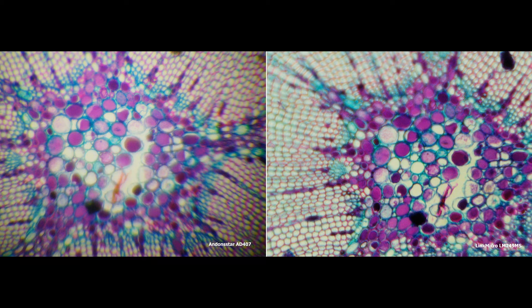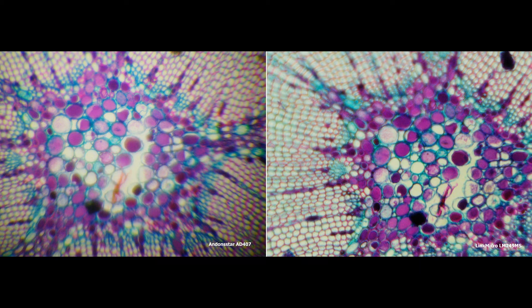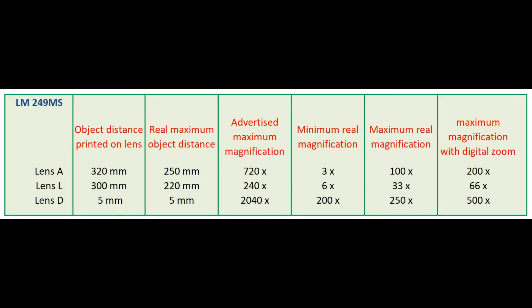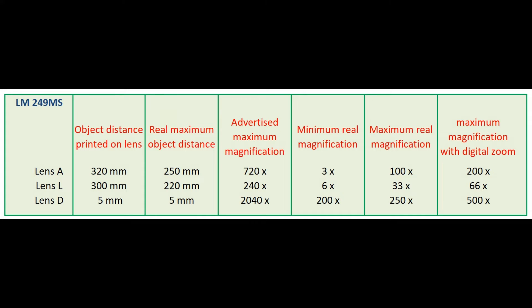A lot of nonsense is written about the maximum magnification of a microscope, mainly by the advertising department. Anyone who has worked with these instruments knows that for high magnifications you need oil immersion objectives. The many transitions from the glass of the lenses to the air between the object and the lens, from the air back to the glass of the slide ensure that more than say 400 times magnification without these special oil immersion lenses make no sense.